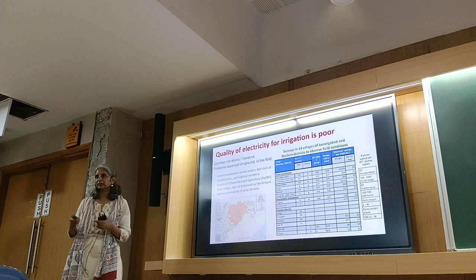Right, so this is some more detailed data. Essentially, one of the major problems, cost-wise as well as in its effect on the farmers, is distribution transformer failure. If a distribution transformer fails, it affects the 25 to 30 farmers who are connected to that transformer. It takes about 8 days to a month, sometimes even up to 2 months, for that transformer to be repaired. In that time, farmers may not be able to irrigate, leading to loss of yield, or they might have to spend on diesel. Richer farmers may spend on diesel or drag a cable from a neighboring DT, a distribution transformer, to get power.